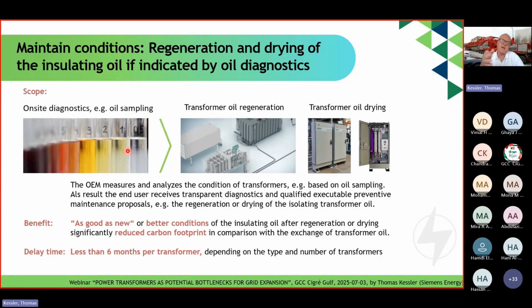Then the transformer oil, in a second step, can either be regenerated, where we take aggressive chemicals out of the oil that attack, for example, the paper of the winding, or we take the moisture out of the oil by applying oil drying.